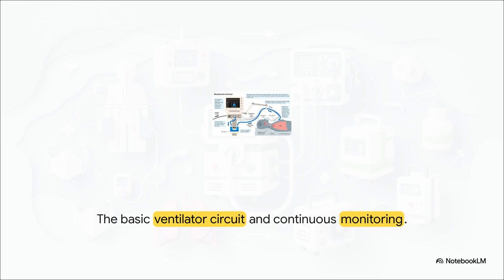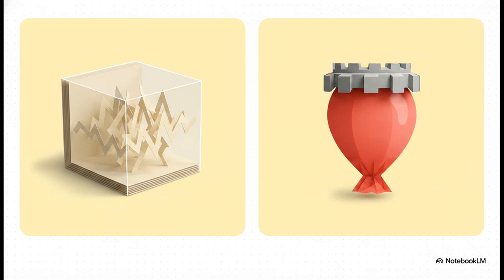The machine pushes a really precise mixture of warmed, perfectly humidified air and pure oxygen down into the patient's airway, and then it passively lets the exhaled air flow back out. But the real magic, the thing that makes this safe at all, is the continuous monitoring. A modern ventilator is basically a high-powered, real-time computer. It is constantly measuring pressure, volume, and flow. It literally translates the physical stiffness of a patient's lungs into digital waveforms on a screen that clinicians can read instantly.